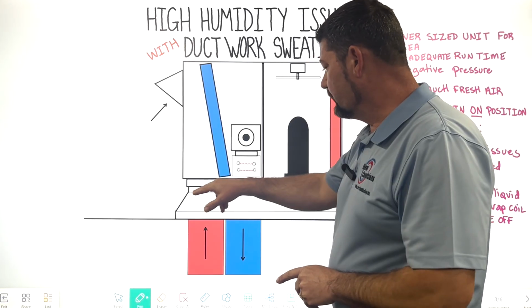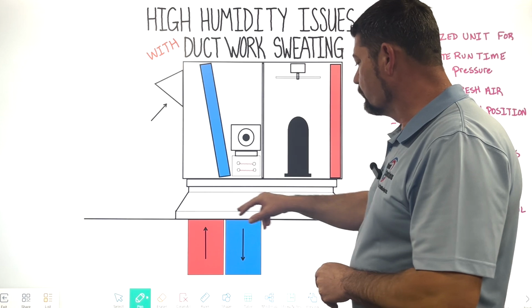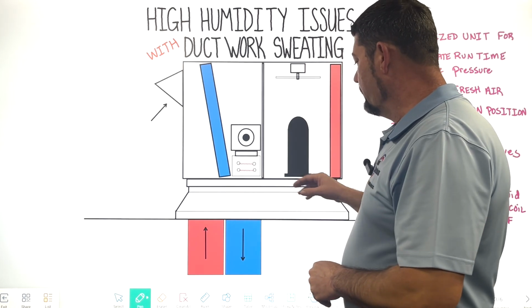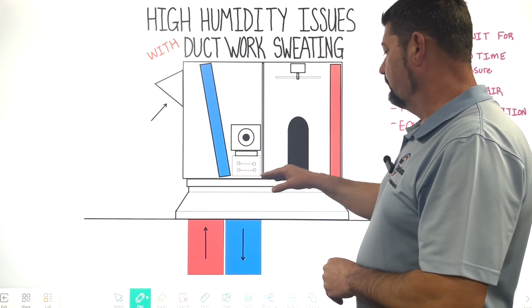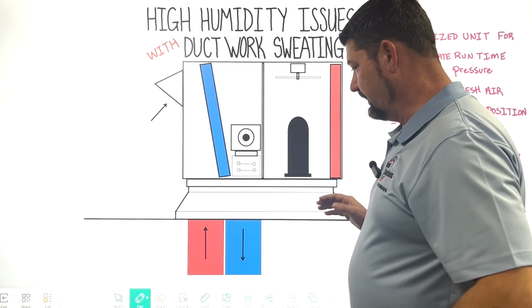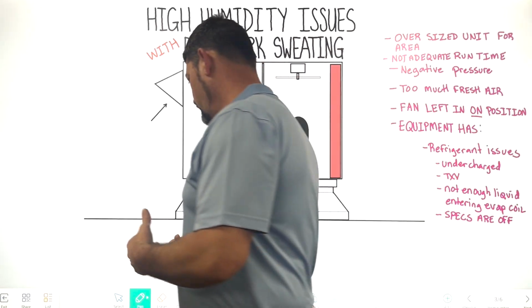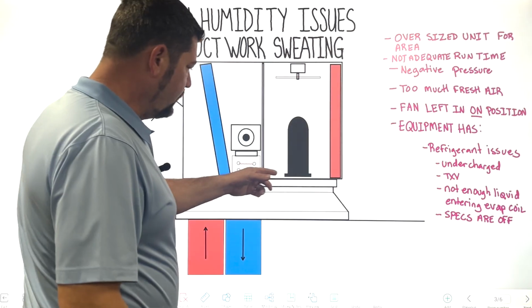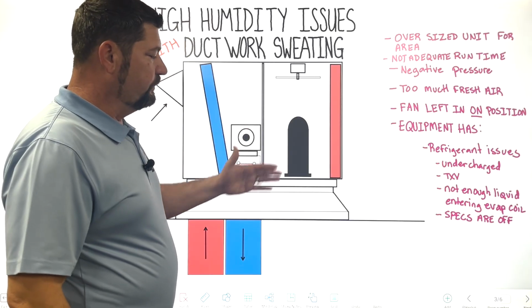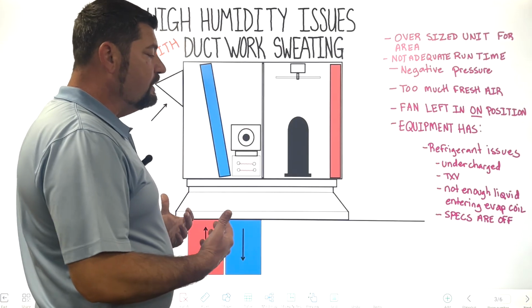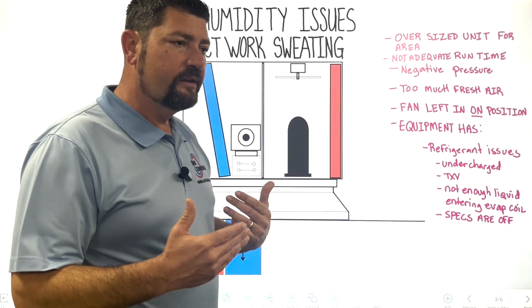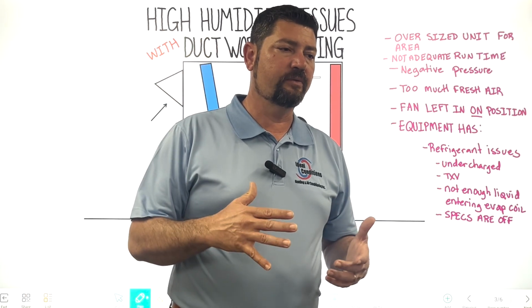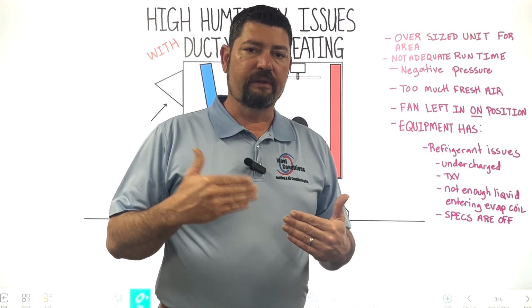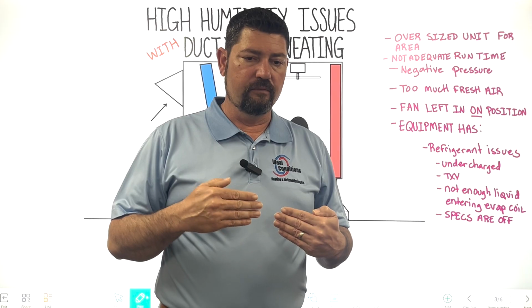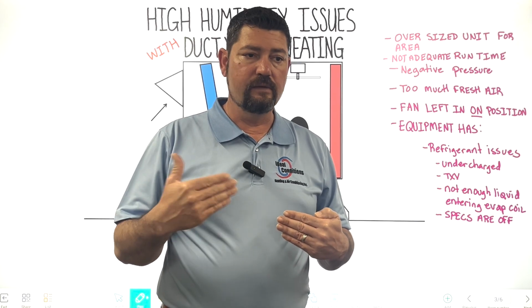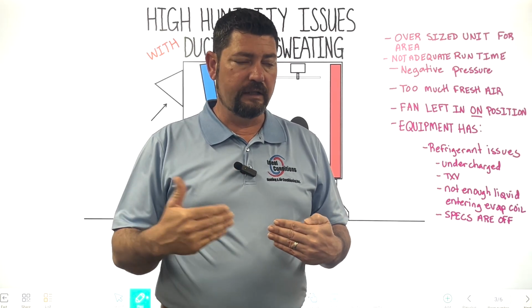Maybe it just rained and the curb is wet, and they're thinking, oh, you got a roof leak. Or maybe there's things that have been done inside this package unit where people have drilled holes to bring in electrical whips, and those electrical whips aren't siliconed very well, and you don't know where the water's coming in at. And maybe you're thinking, well, the pattern is every time it rains or it stops raining, they complain about there being sweating or water, right? We don't know if it's sweating or if it's just a leak.